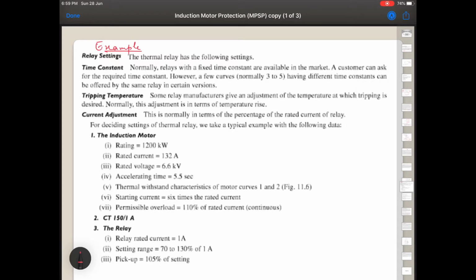Now in this example, we'll try to understand how to set a thermal relay, meaning its current and its time, and other aspects of a current relay, how to do the settings of it. So the thermal relay has the following settings. Time constant: generally relays with fixed time constants are available in the market. However, normally 3 to 5 curves having different time constants are offered by the manufacturer for a certain relay with certain versions.